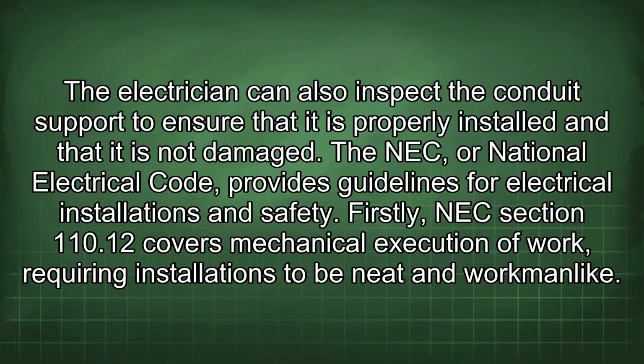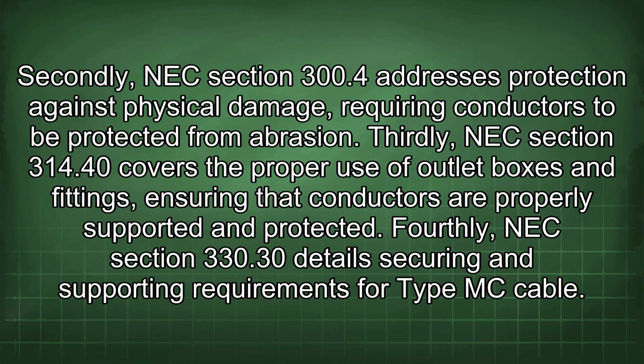The NEC, or National Electrical Code, provides guidelines for electrical installations and safety. Firstly, NEC Section 110.12 covers mechanical execution of work, requiring installations to be neat and workmanlike. Secondly, NEC Section 300.4 addresses protection against physical damage, requiring conductors to be protected from abrasion. Thirdly, NEC Section 314.40 covers the proper use of outlet boxes and fittings, ensuring that conductors are properly supported and protected. Fourthly, NEC Section 330.30 details securing and supporting requirements for Type MC cable.